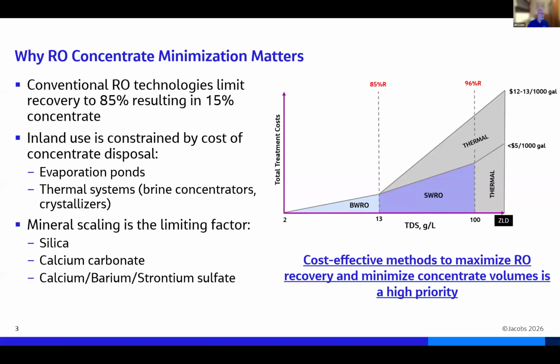Why does RO concentrate minimization matter? Conventional RO technologies typically used for brackish water treatment are limited in recovery to 85%, so this gives us a fair bit of concentrate we have to dispose of. For inland sites where a lot of brackish groundwater exists, that constrains the cost of the overall project, particularly concentrate disposal, because we have to use evaporation ponds or thermal systems like brine concentrators, which are quite expensive. Evaporation ponds also sometimes create environmental issues associated with their siting and operation. Mineral scaling is generally the problem we have in trying to push RO recoveries, silica in particular, but also calcium carbonate and sulfate salts. So what we want to do here is try to reduce that scaling potential to allow us to use RO to get to a maximum recovery.